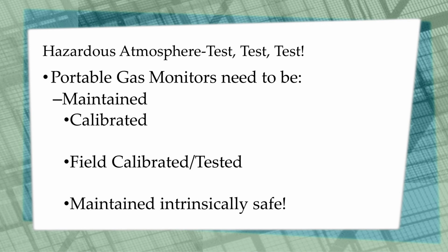I also encourage people to test them when you're out at the site. Before you start testing the air that's inside a trench or permit required confined space or anything else, take them outside where you know the air is fresh. Take them where there's not any traffic, and make sure that the actual monitor is working correctly. If all you care about is putting the numbers down on a sheet of paper and not trying to figure out if that machine's giving you good information, there's potential there for somebody to get hurt or worse.